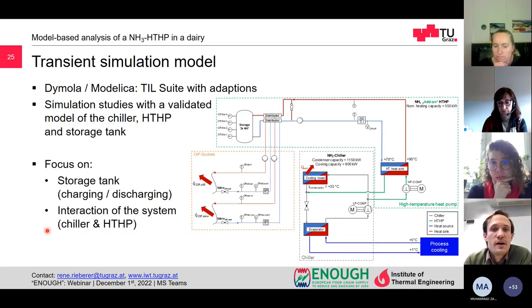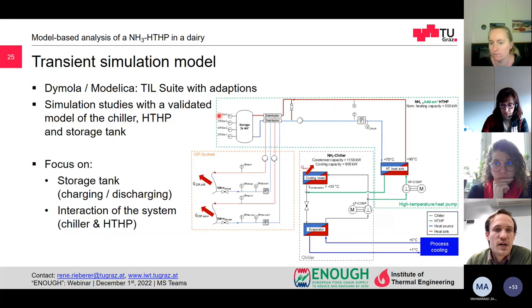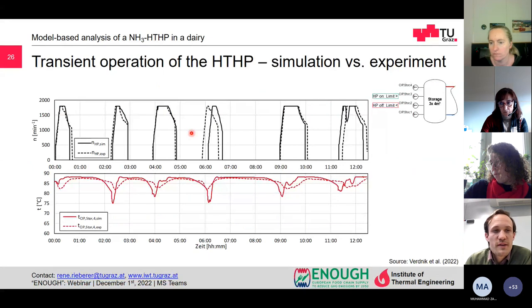Therefore, a transient simulation model has been set up in the software Dymola Modelica with TIL. This was already validated with measurement data. The focus is on the charging and discharging of these buffer storages and the interaction of the system, so the chiller and the high temperature heat pump. I will only show you one example of the simulation in comparison with the experiments. What we can see here is the rotation speed of the high temperature heat pump compressor and the temperature of the storage tank. The operation of the high temperature heat pump was done by the limits of the temperatures in the storage tank.